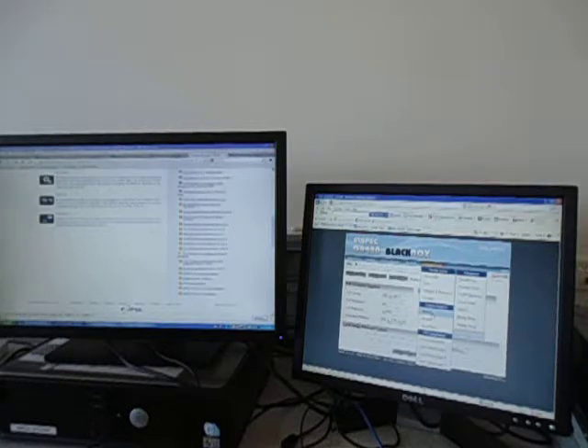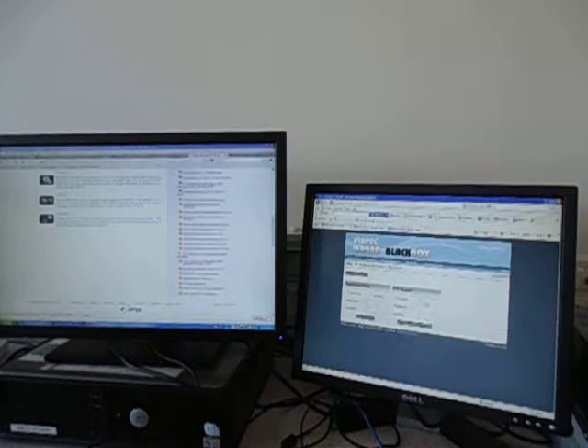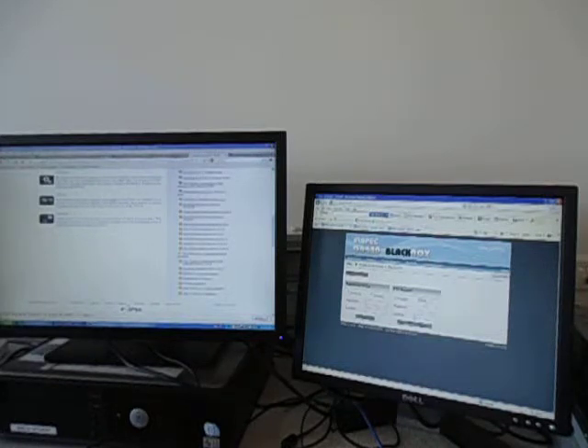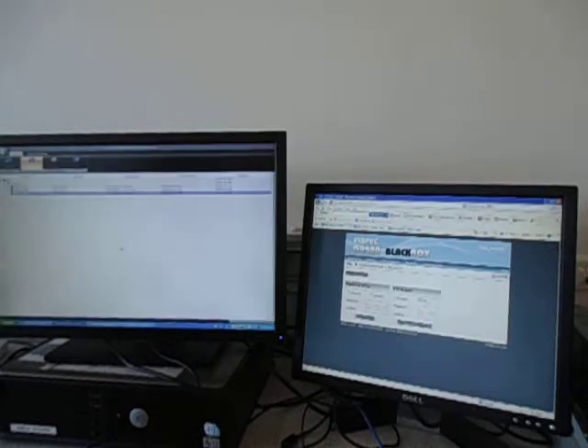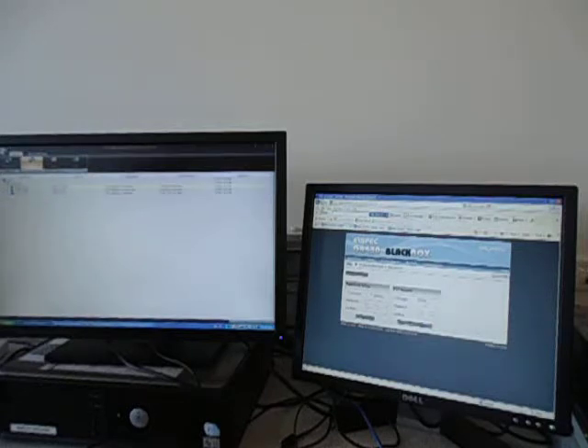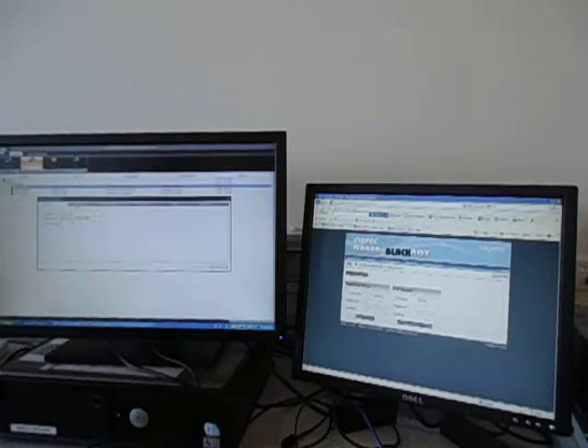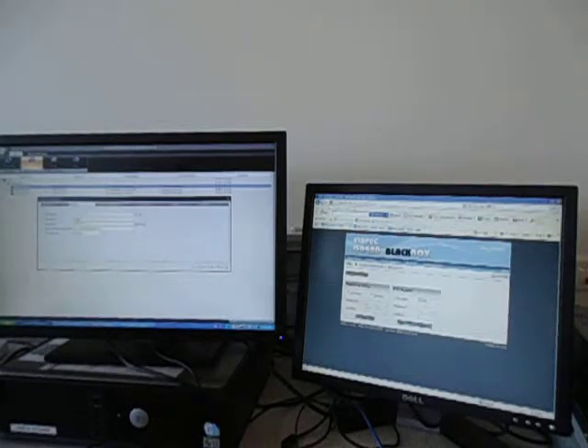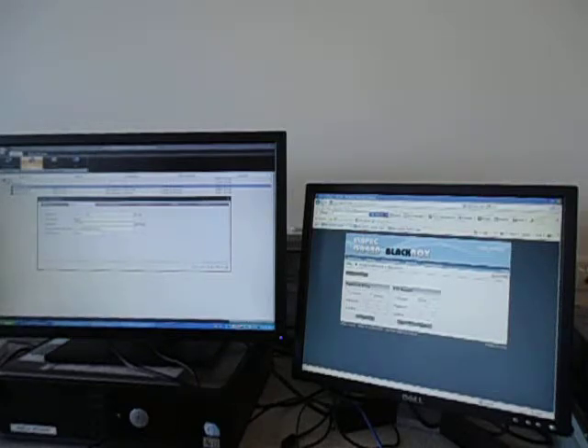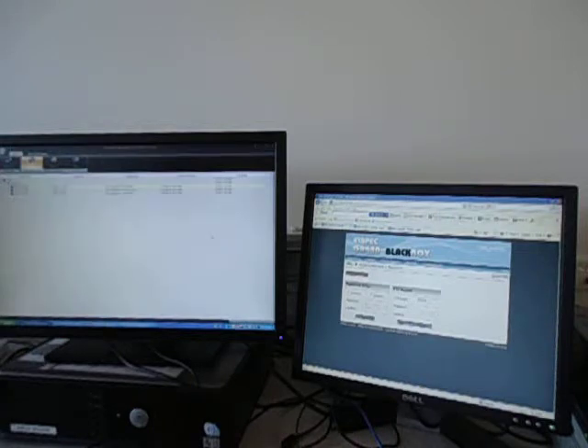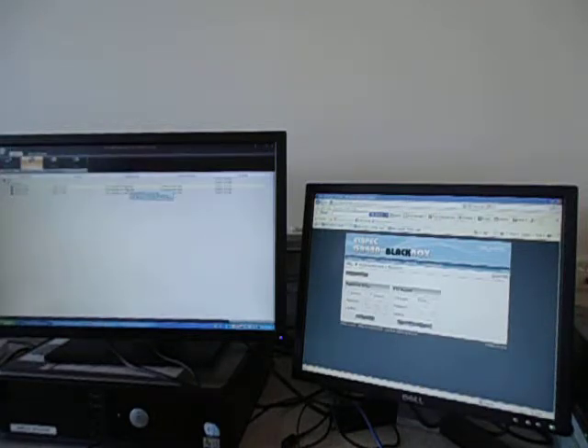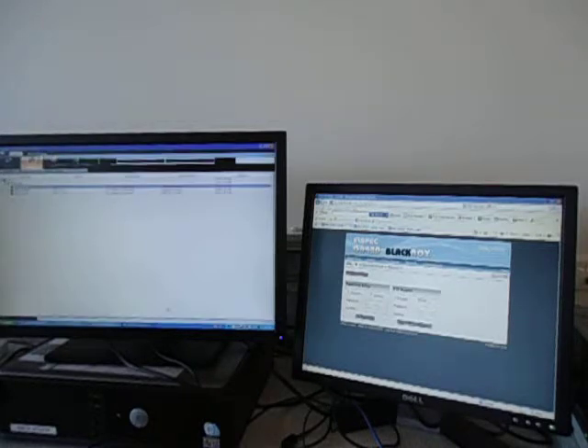The other thing that I had to do was go to security and then just update the FTP login. So the FTP user, I won't show you my password, but I updated the password. Then I've gone in here and right click configuration and make sure that you know the name. I actually had to change the name and the device IP address because I've actually changed the black box unit that I was using. There's your FTP username and FTP password, which I won't show, but once I've done that it was fine.